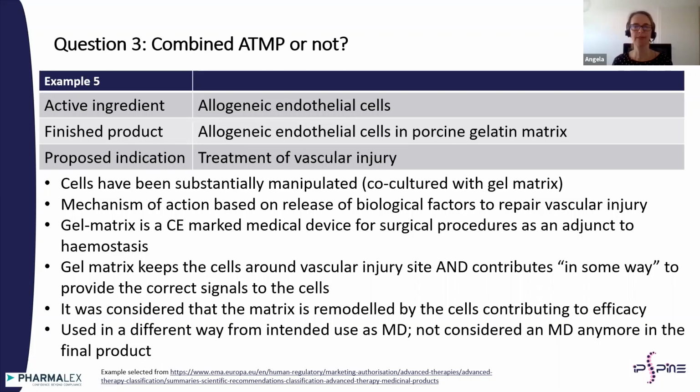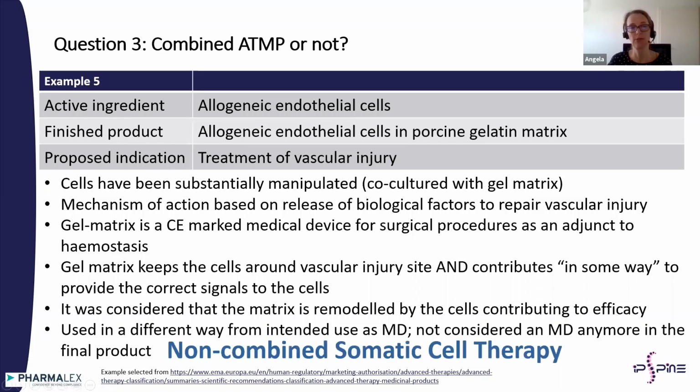So the medical device here is apparently not just a piece of furniture sitting there and providing the scaffold, but something alive, talking, speaking, modulating. For this reason, the agency considered that the product is used in a different way from the intended use as a medical device, where apparently the matrix is just put onto the injury to hold everything together. But in this case, together with these endothelial cells, it is something living and active. So it's not a medical device anymore, and the agency concluded it's a non-combined somatic cell therapy.